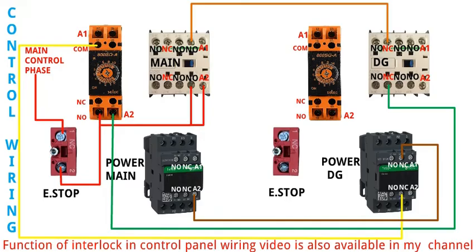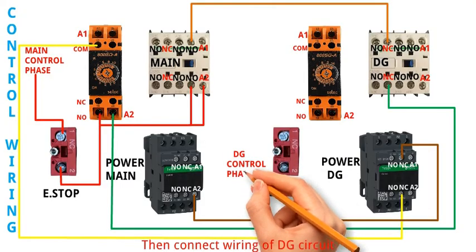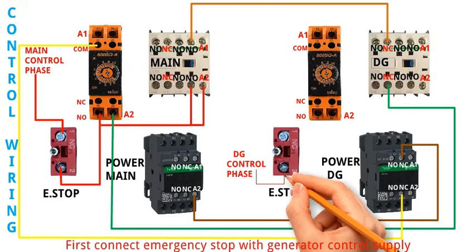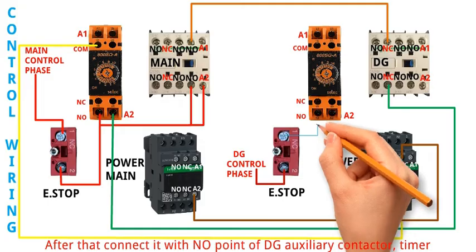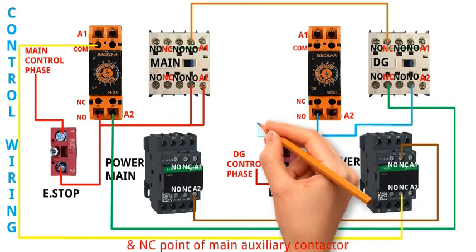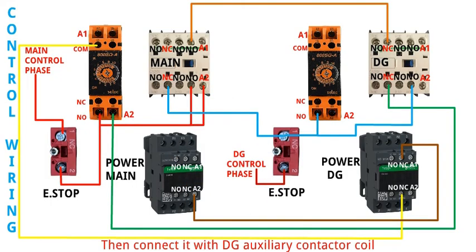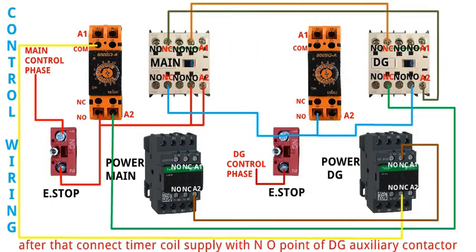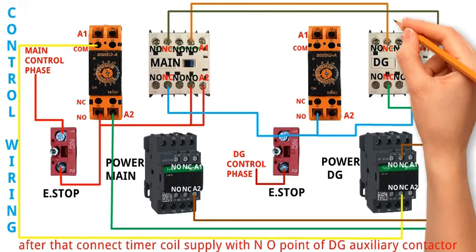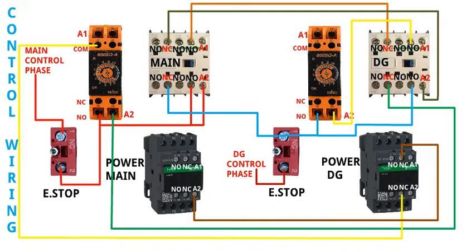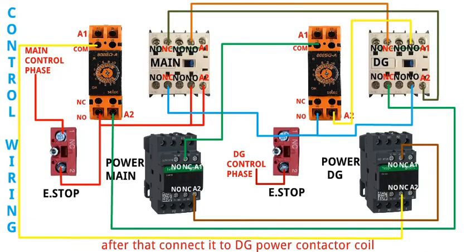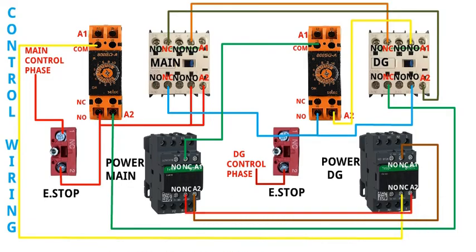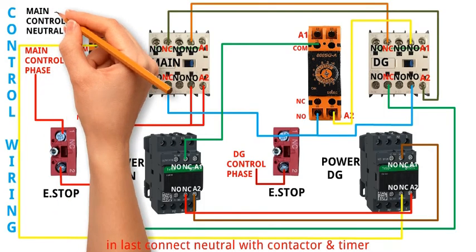The function of interlock in control panel wiring video is also available on my YouTube channel. Now connect the wiring of the DG circuit. First connect the emergency stop with the generator control supply. After that connect it with the NO point of DG auxiliary contactor, timer, and NC point of main auxiliary contactor. Then connect it with the DG auxiliary contactor coil. After that connect the timer coil supply with the NO point of DG auxiliary contactor. Then connect a wire from DG timer to the main power contactor NC point. After that connect it to the DG power contactor coil.